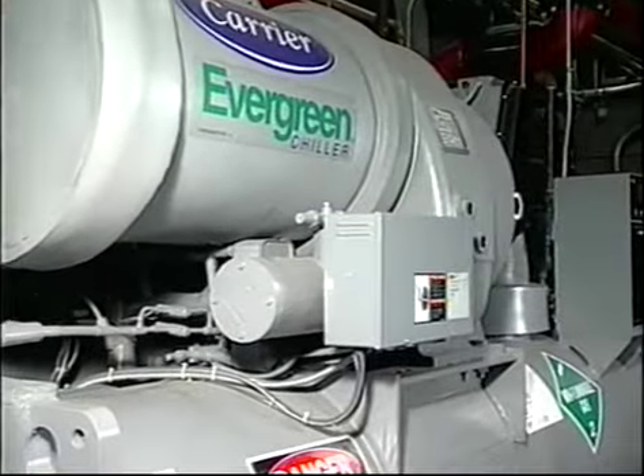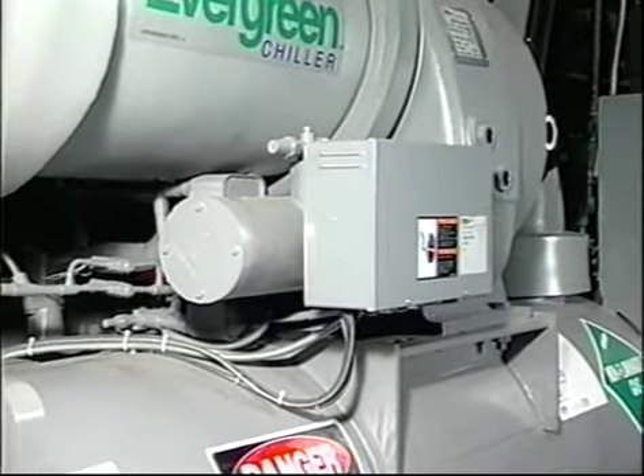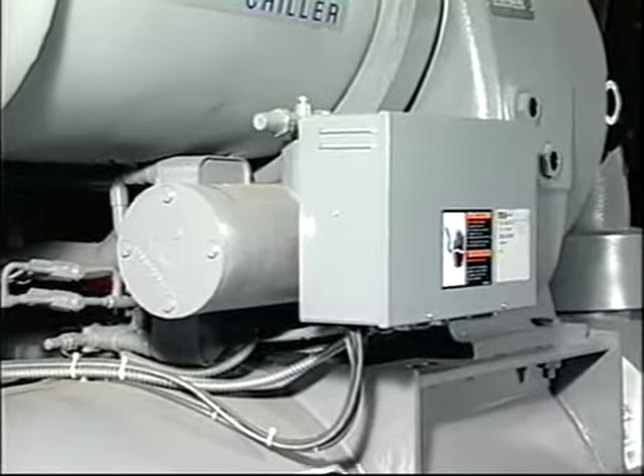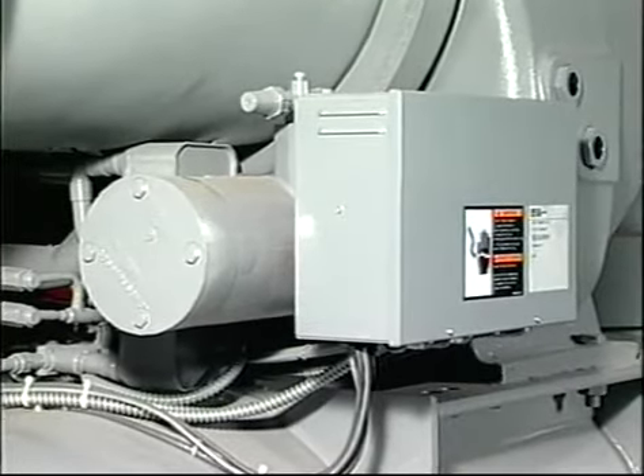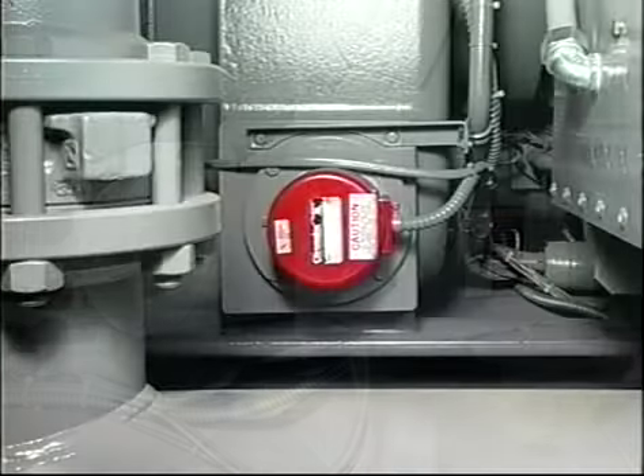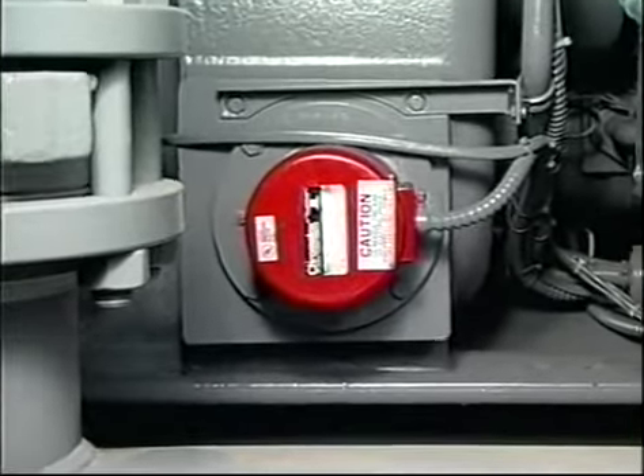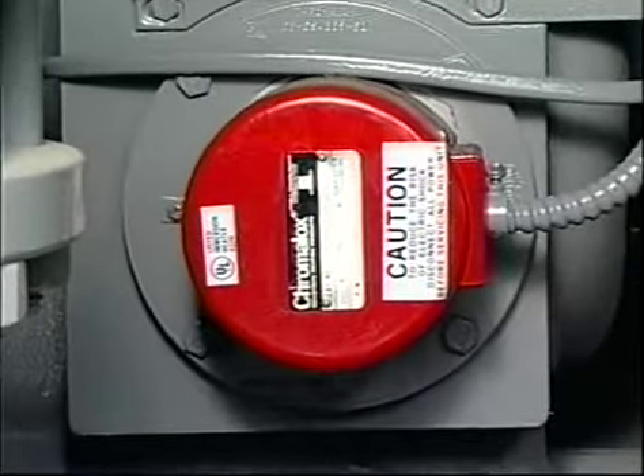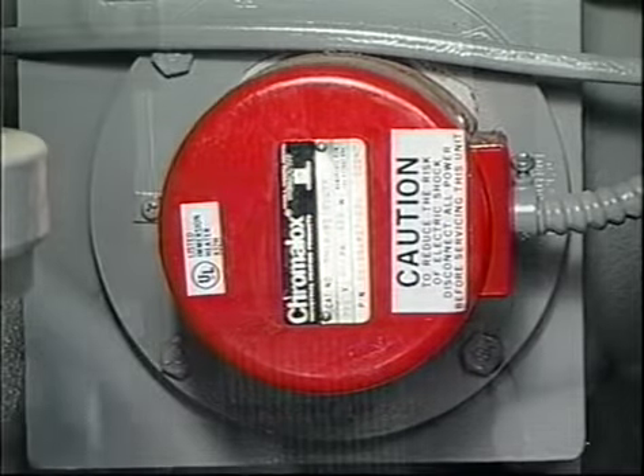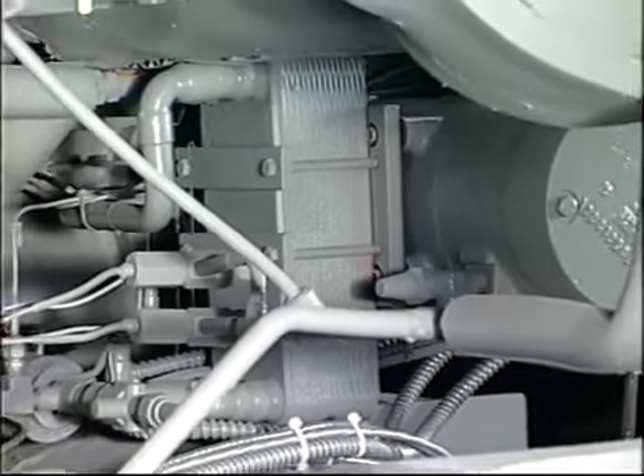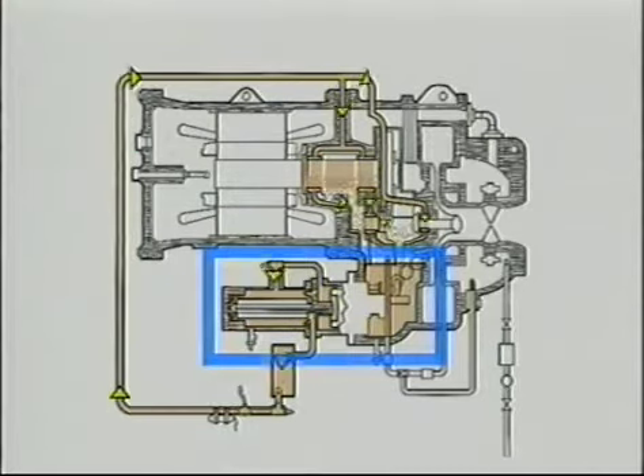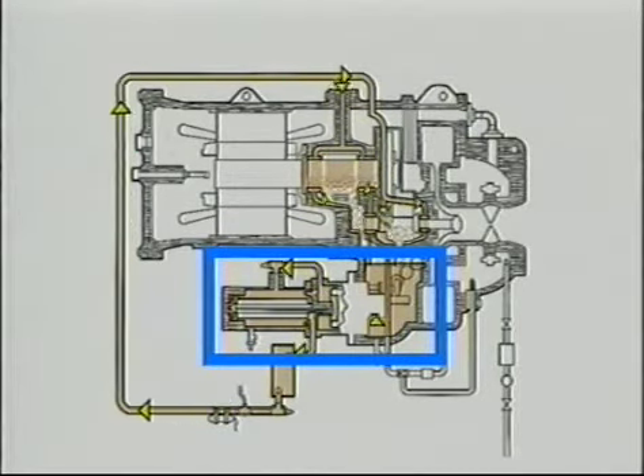The compressor contains an external oil pump driven by its own electric motor. It is mounted in the transmission oil sump and circulates oil to the main bearings and transmission gears. The crankcase contains an electric heater to keep the oil warm when the compressor is not running, to prevent the oil from absorbing refrigerant, which would dilute it. An external oil cooler is provided to cool the oil when the compressor is running. Oil from the pump discharge passes through the oil pump motor and serves as a coolant. Oil pressure is regulated by a relief valve that's located internally. The valve relieves the pump discharge back into the oil sump, maintaining proper oil system pressure.